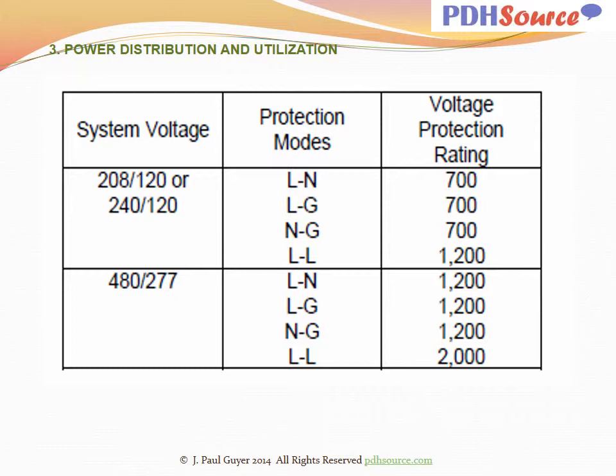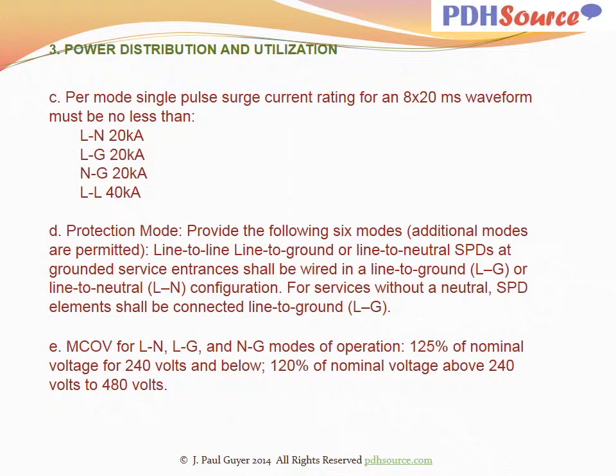This table provides the voltages, the protection modes, and the voltage protection ratings. LN is line to neutral, LG line to ground, NG neutral to ground, LL line to line. Per mode single pulse surge current rating for an 8x20 waveform shall be no less than as indicated. Protection mode, provide the following 6 modes. Additional modes are permitted: line to line, line to ground, or line to neutral.